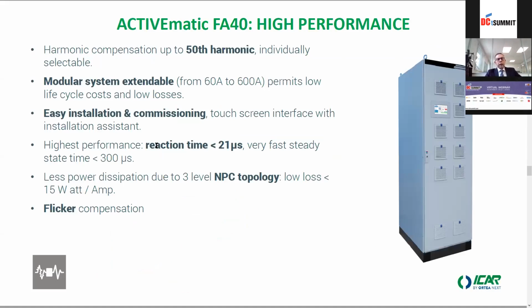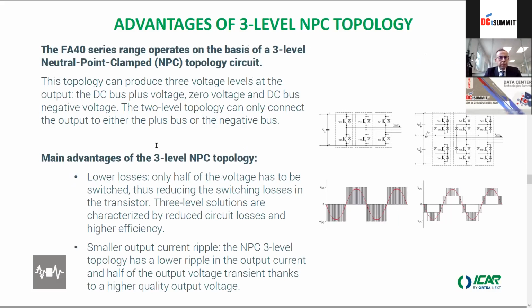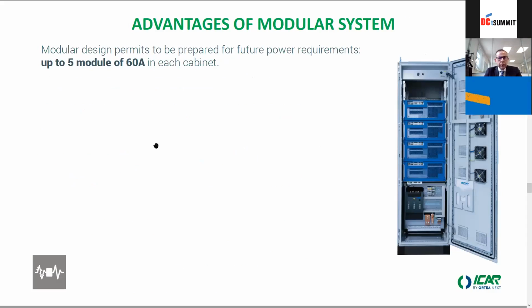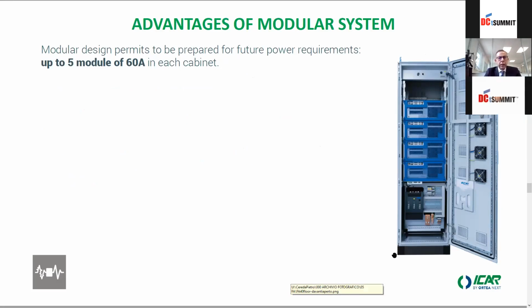So the active filter is very easy to install at the end, because it's like a power factor correction system, very easy to install, and will help you to have a better energy quality. Well, the modular system will help in having the possibility to improve the power of an active filter if you want. So you can start with 60 amps and then increase the power step by step.